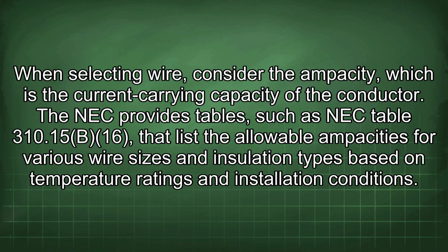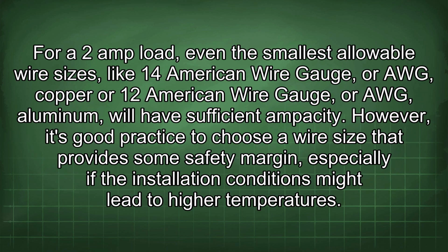When selecting wire, consider the ampacity, which is the current carrying capacity of the conductor. The NEC provides tables, such as NEC Table 310.15(B)(16), that list the allowable ampacities for various wire sizes and insulation types based on temperature ratings and installation conditions. For a 2 amp load, even the smallest allowable wire sizes, like 14 American wire gauge, or AWG, copper, or 12 American wire gauge, or AWG, aluminum, will have sufficient ampacity.